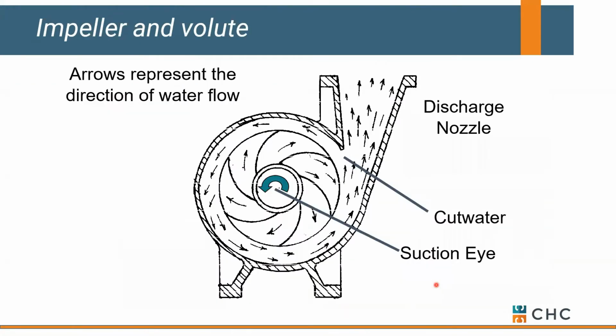Take that impeller and put it into a typical pump housing. This is what you're looking at for a standard centrifugal pump. Again, all water is flowing into the eye, okay? Holes around our coffee can, and then vanes that direct it out or flip it towards the discharge in this case. Now, if you understand this, you've got any centrifugal pump that's out in the marketplace, because they all work the same. Orientation might be a little different.